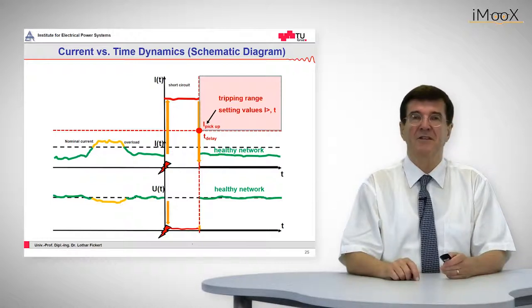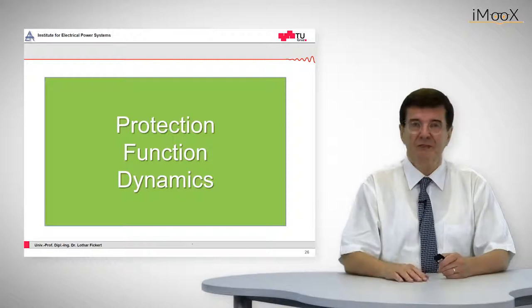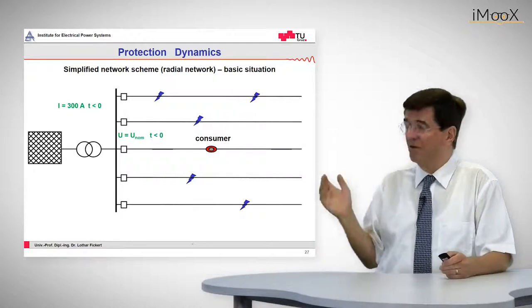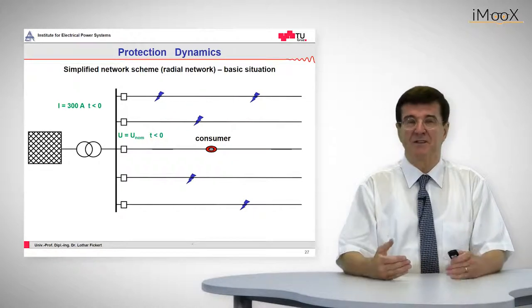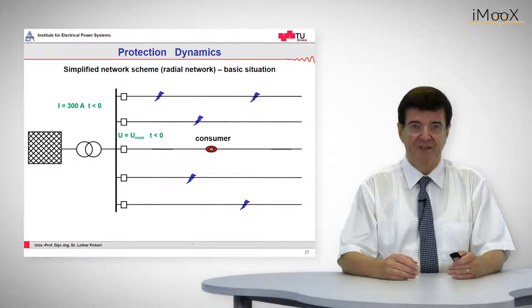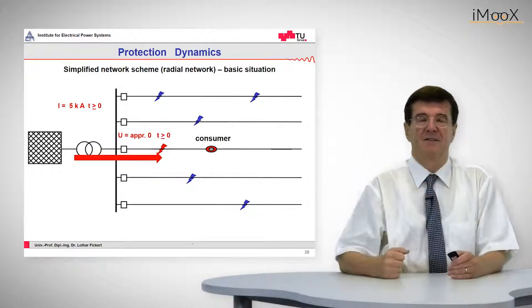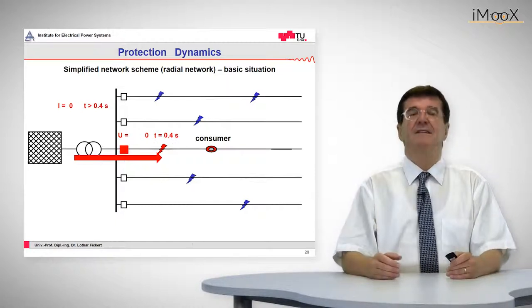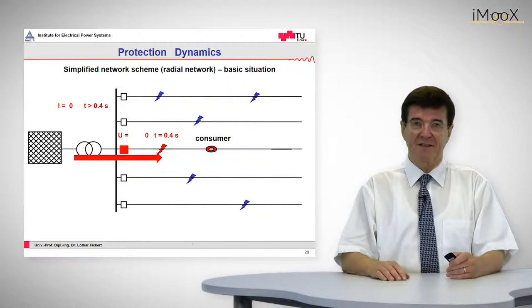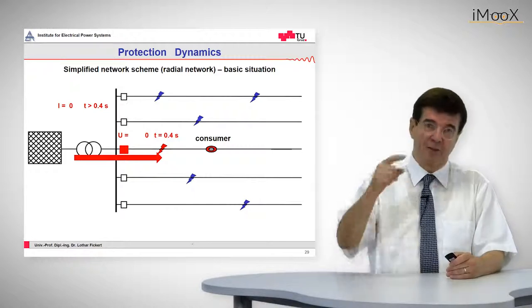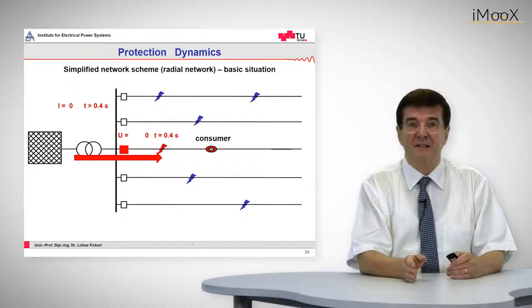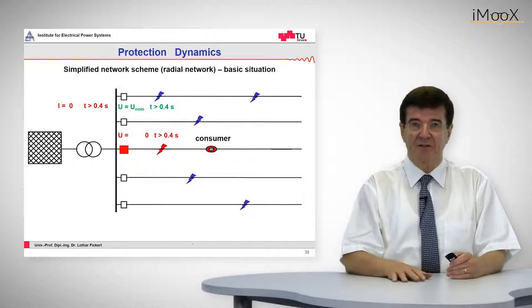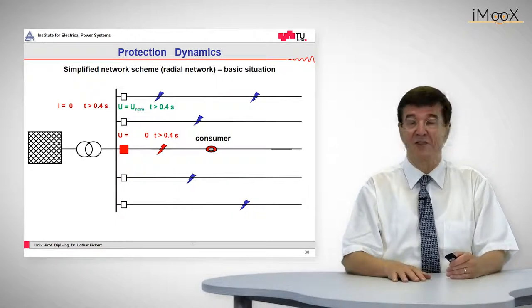So this was the voltage and current dynamics versus time. Now let's see what the protection function does in this situation. Before something happens, the current on this feeder is some 300 amps and the voltage is nominal. When the fault occurs, a big current comes from the source to the fault — these typical 5 kilo-amps. The voltage breaks down and the time starts to run until it has elapsed, at which point the protection operates the circuit breaker. The circuit breaker trips the current path, the feeder is switched off, and the remaining network is healthy again with the voltage recovered.